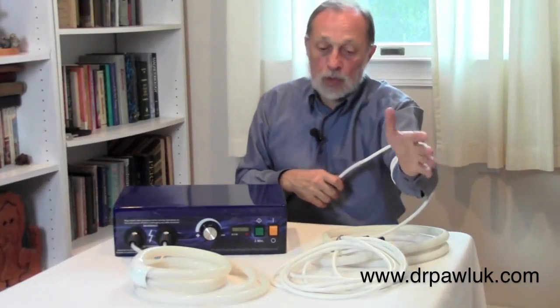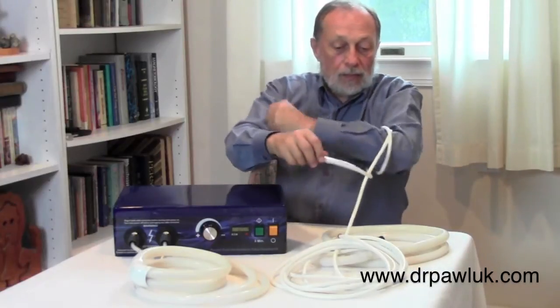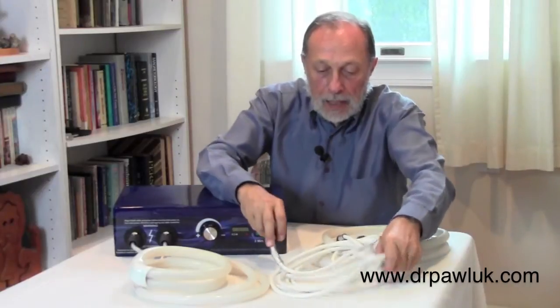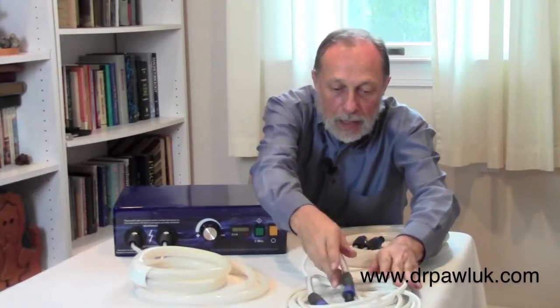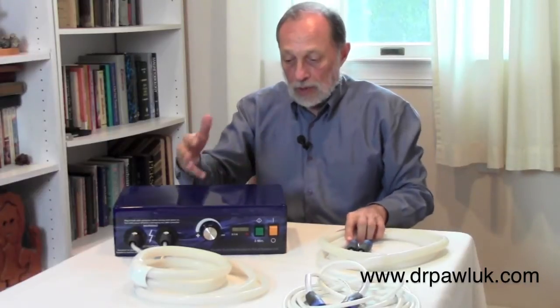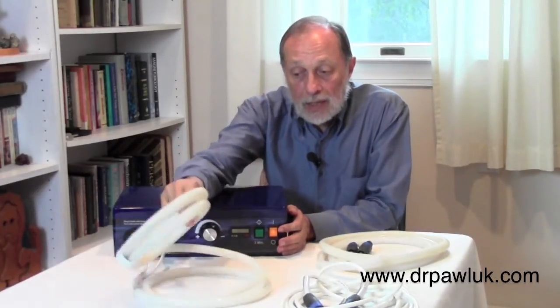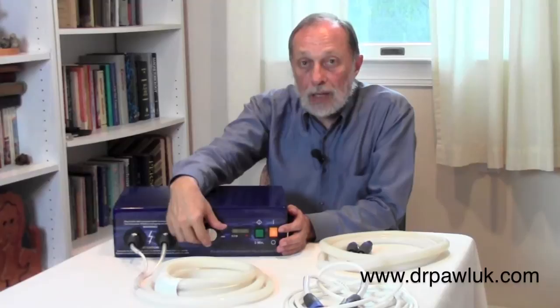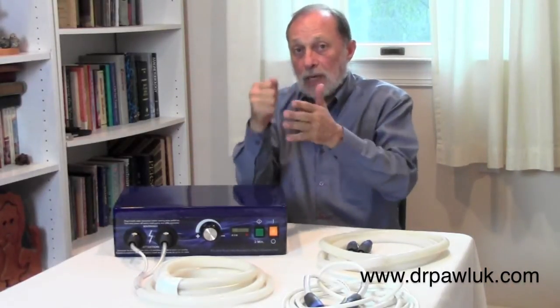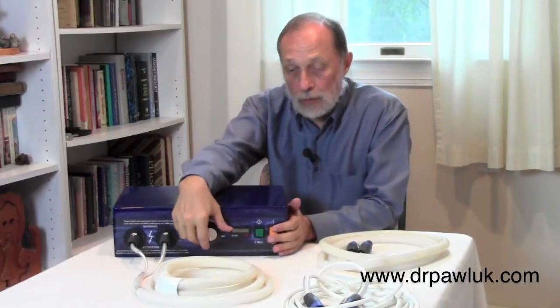The rope coil would be used primarily for the extremities. It produces a nice high field very locally, and can wrap an entire extremity as opposed to the other coils, which don't really allow for that. Once we actually get this activated, you're going to hear a clicking sound, and you know that power is coming — that's the wires themselves banging against each other because of the amount of charge running through them.